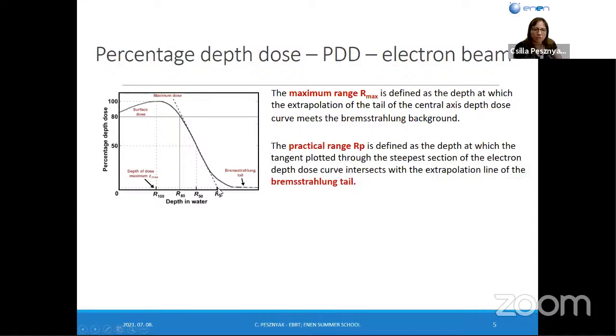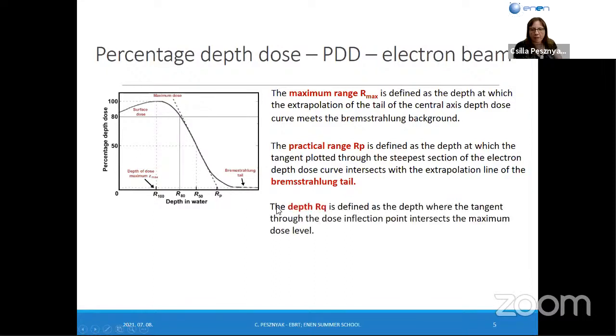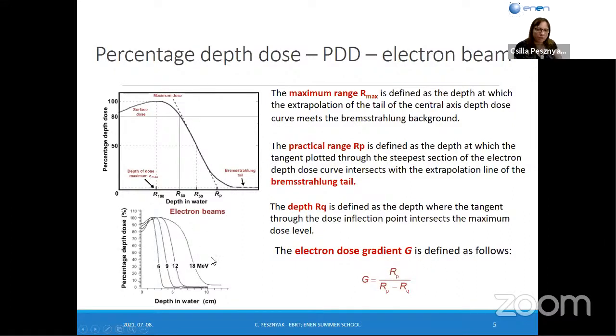Then the second one is the practical range, RP. This is defined as the depth at which the tangent plotted through the steepest section of the electron depth dose curve intersects with the extrapolation line of the bremsstrahlung tail. This is the bremsstrahlung tail. Then depth RQ. The RQ depth is defined as the depth where the tangent through the dose inflection point intersects the maximum dose level. After that, we can calculate the electron dose gradient, G. Here is the definition. And you can see for the electron beam there is a different shape of PDD, depending on the energy.